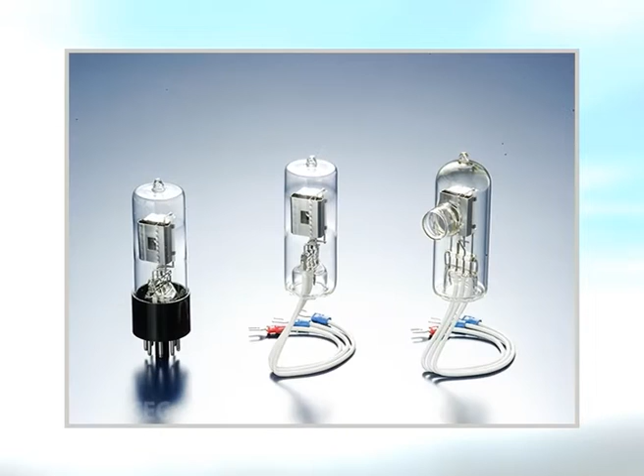Tungsten filament lamps and hydrogen deuterium lamps are most widely used and suitable light sources, as they cover the whole UV region. Tungsten filament lamps are rich in red radiations. More specifically, they emit the radiation of 375 nanometer, while the intensity of the hydrogen deuterium lamps falls below 375 nanometer. Number second is the monochromator.